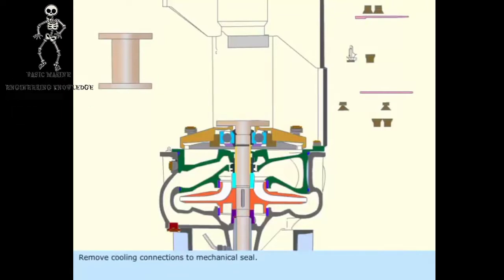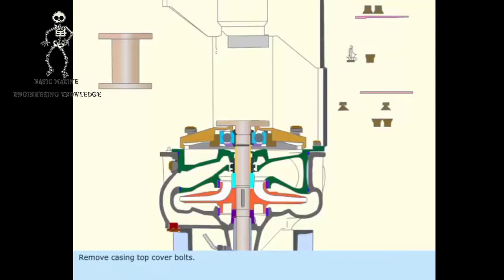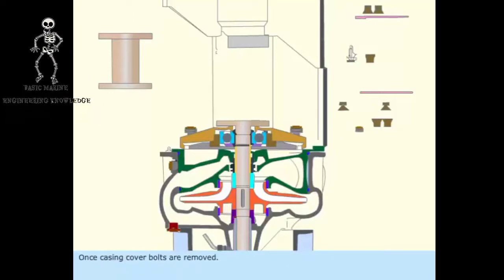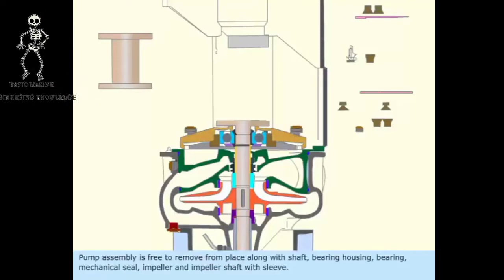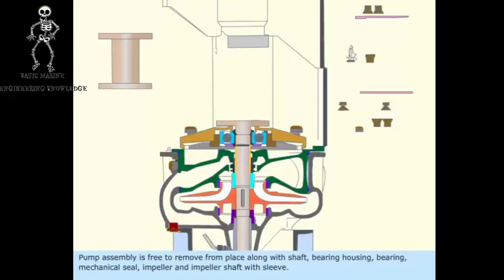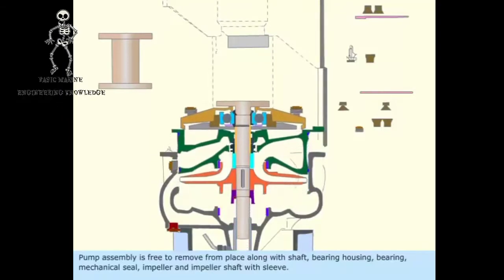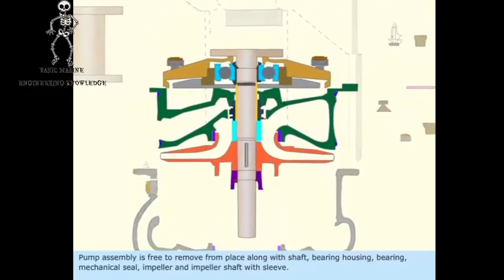Remove cooling connections to mechanical seal. Remove casing top cover bolts. Once casing cover bolts are removed, pump assembly is free to remove from place along with shaft, bearing housing, bearing, mechanical seal, impeller, and impeller shaft with sleeve.